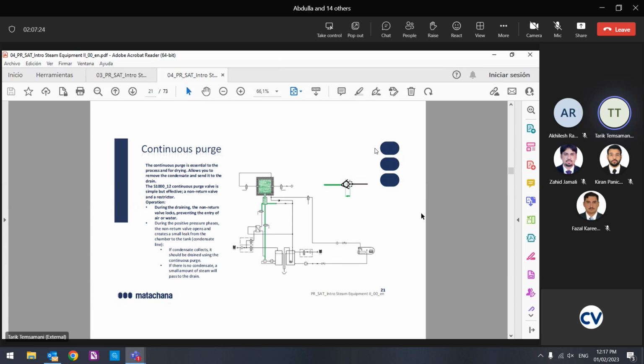So once we put steam in the jacket, the contact of the steam with the surface of the chamber gives us different temperatures and gives us condensate. So we have to remove this condensate. For the jacket we use a purger, the automatic purger. It works with temperature. It opens and removes the water. Once it is steam, at hot temperature, it closes. If we have water here, it opens and we remove the water. When the water is removed and I get steam, it closes.